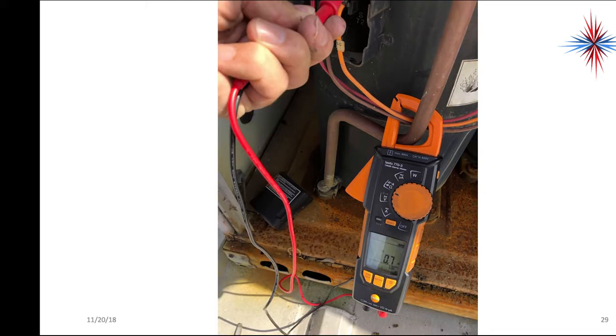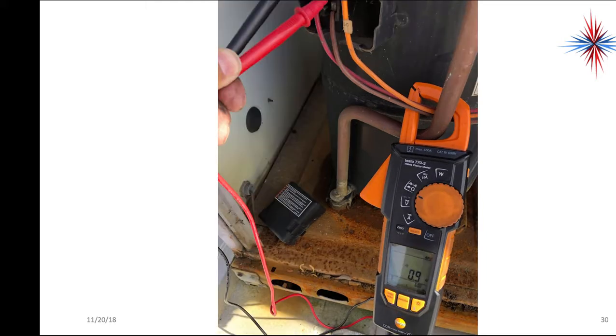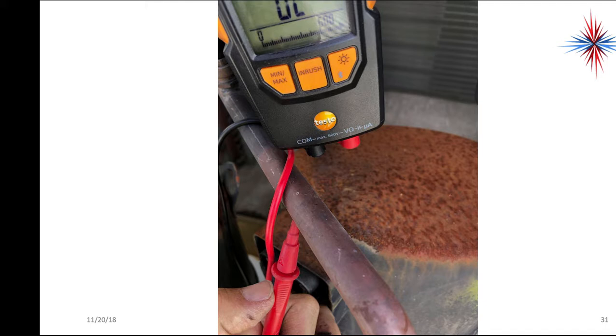0.9, 0.7, 0.9. This is a three-phase compressor. They should all be relatively close. I'm fine with that. Repeated the same for the second compressor. So we knew our compressor windings were good. Now the other thing that I always check is every single terminal to ground. Okay, and I'm looking for OL. I don't want any terminals to have any current path to ground. Okay, that signifies that a compressor might be grounded out.